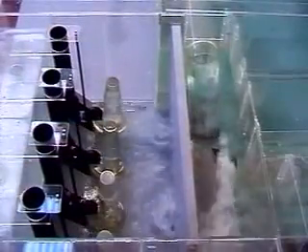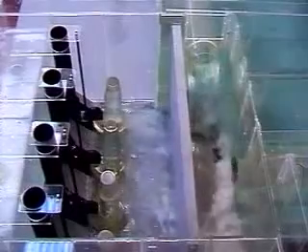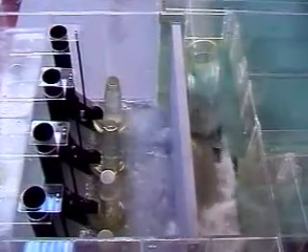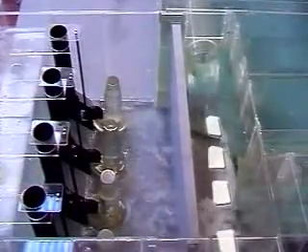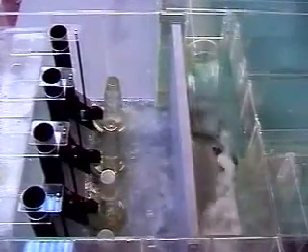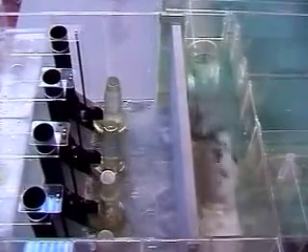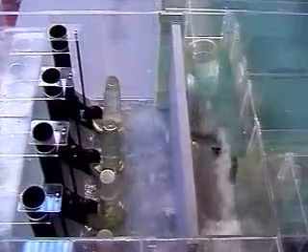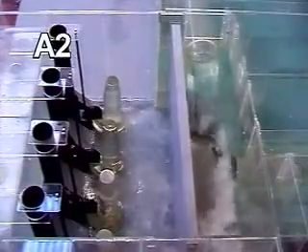If the piping system and the sump location do not allow for a front entry inlet, a side entry inlet with a baffle wall modified with ports can be used. This configuration, which Flygt has also invested significant research into, is referred to as type A2. In this design, the baffle wall redirects the incoming flow and distributes the flow evenly towards the pump through the ports.